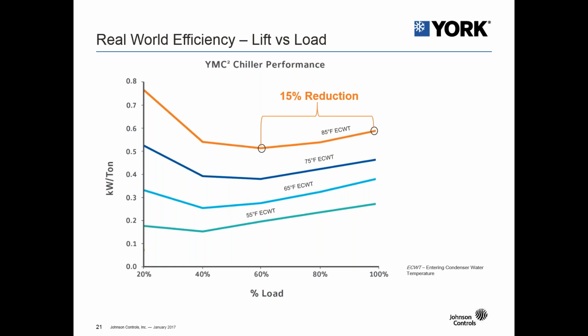So if we were to maintain a constant 85 entering condenser water temperature and see a load reduction on the chiller from 100% load down to 60% load, in terms of kW per ton, that would be a 15% reduction in kW per ton. However, if we keep the load at 100% and we go from a 85 entering condenser water temperature down to 75 degrees, that's a 24% reduction in energy. And if we still maintain 100% load and reduce the entering condenser water temperature down to 55, that's a 59% reduction in kW per ton.